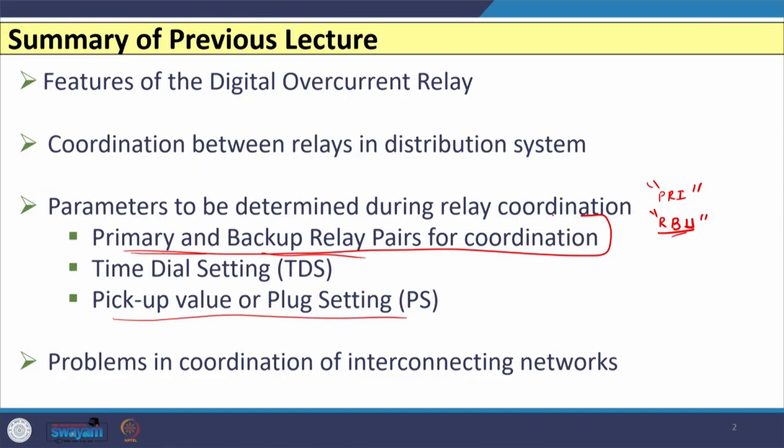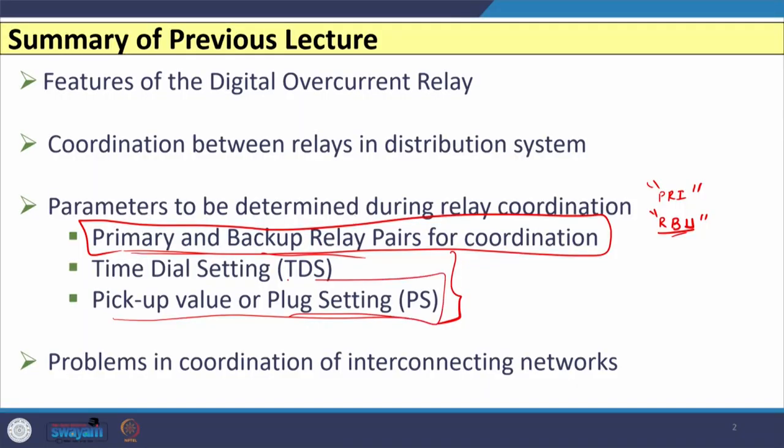The first output is the primary and backup relay pairs (PRI and RBU). The second is the time dial setting, and the third is the pickup or plug setting of the relay. The link net structure gives only the primary and backup relay pairs. The remaining two settings — time dial and plug setting — require load flow studies to establish initial conditions and short circuit studies for time dial calculations, while plug settings are based on full load current with a percentage of overload.